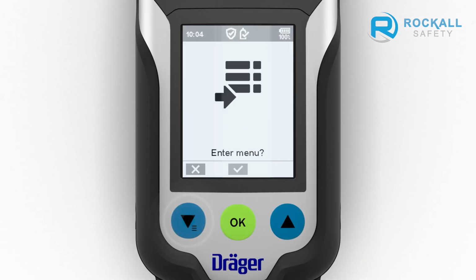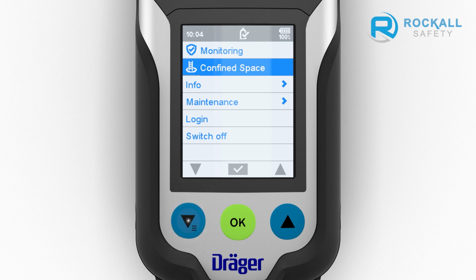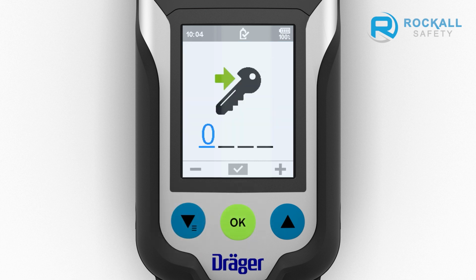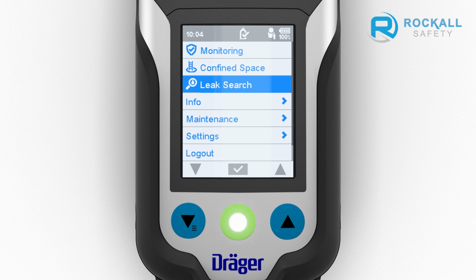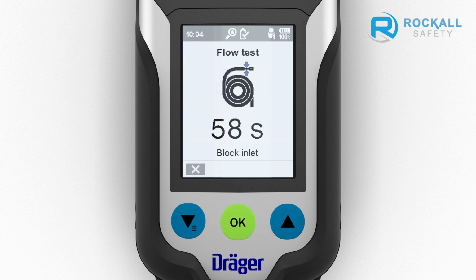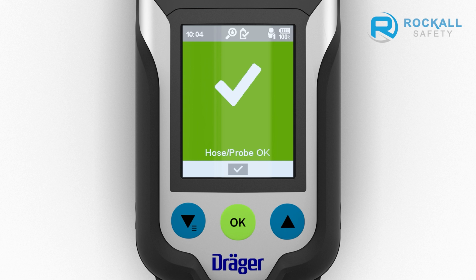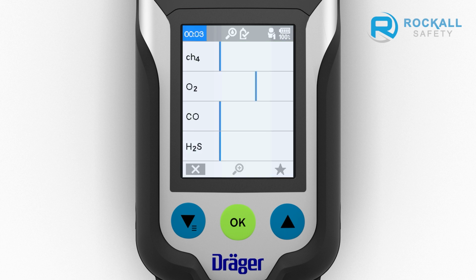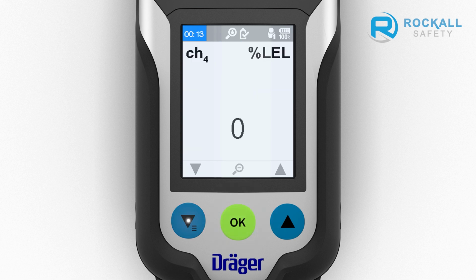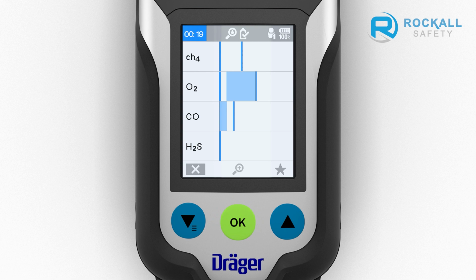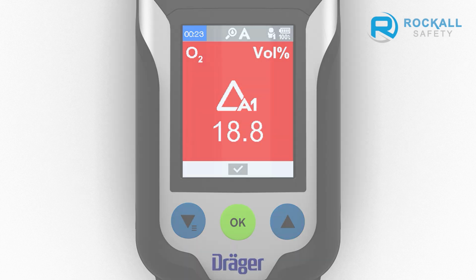The instrument calculates the flooding time based on the entered hose length, the measurement gas setting, and the temperature thresholds. The leak search function has a similar structure. This function is likewise selected via the menu. Once the pump test is completed successfully, a window will appear in which the gases can be displayed in the form of a bar chart. This improves the overview. The diagrams show the current values and the peak values. In single gas view, an audible signal sounds at the same time. The frequency of this signal increases as the gas concentration rises. If a gas reaches the pre-alarm threshold, the gas alarm is displayed.